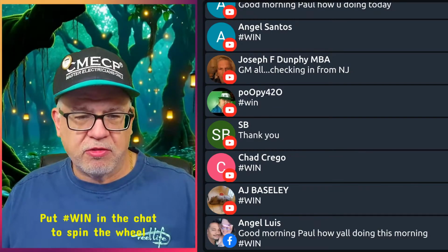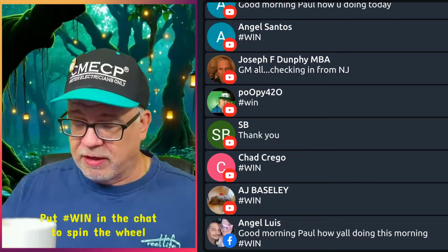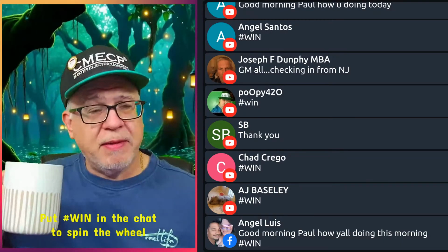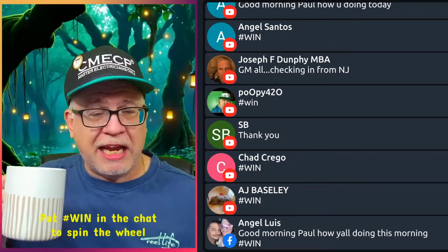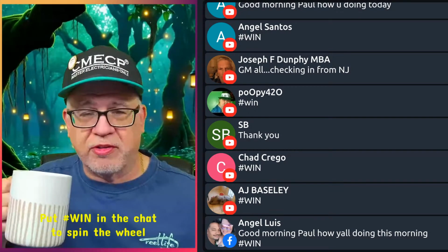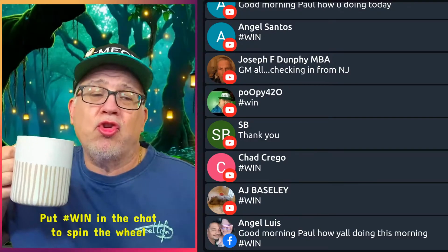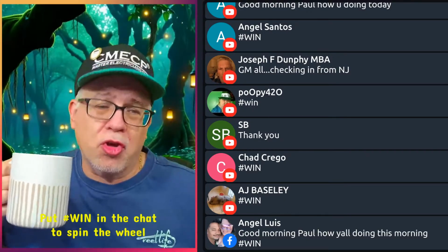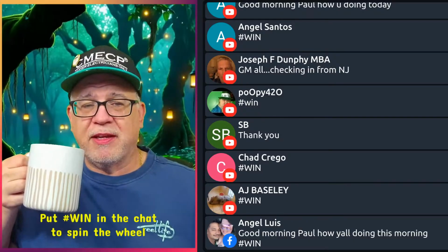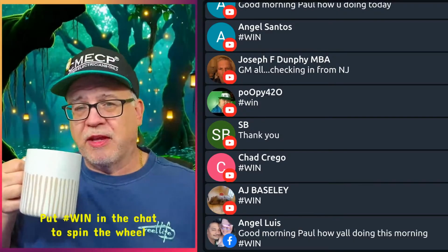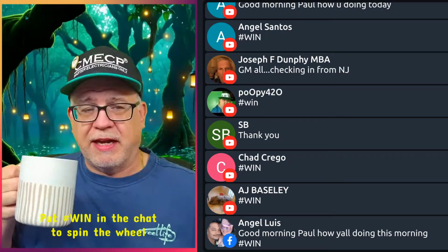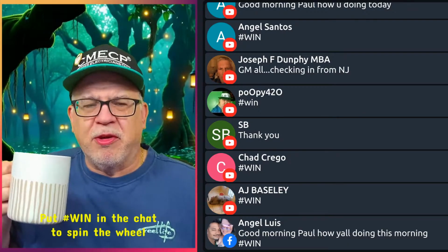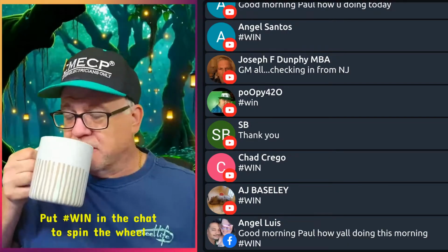MC cable applications. And we still have on social media, by the way, shout out to whoever put that out on social media, people putting videos out and challenging people about using anti-short bushings in MC cable. I mean, you do you, boo. That's what I always have to say to people. You do you. Are they required for MC? They are not. If you use a listed fitting, which you're required to use anyway, 330.6. But it makes you feel better. It makes people feel better to see that bushing in there.